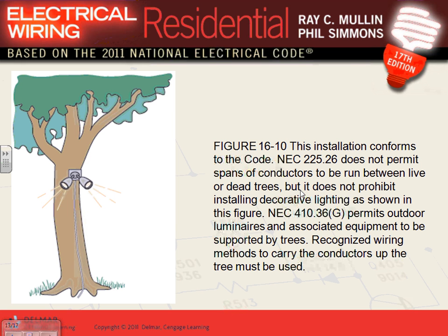Obviously, if this is UF cable, what do you need to do with the UF cable as it emerges out of the ground? Protection with PVC Schedule 80. You have to have protection from physical damage, all the way up to 8 feet or the fixture. Now, any question? Putting a decorative light on a tree, no problem. Now, taking a cable from tree to tree to a third tree, no. You have to have poles.